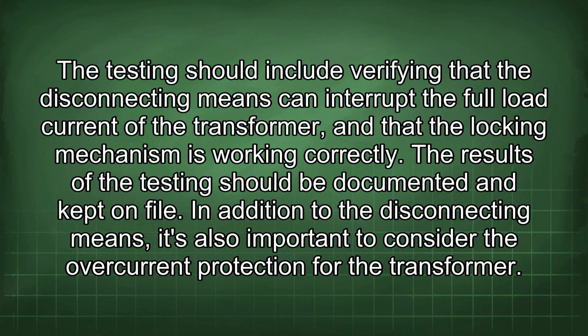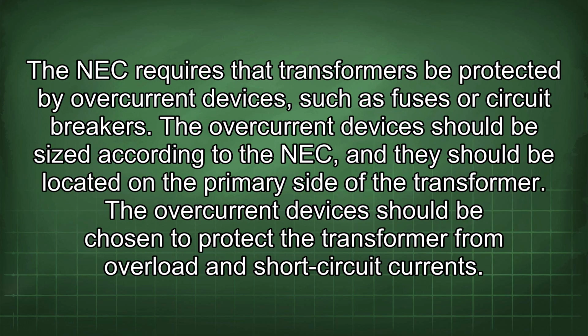In addition to the disconnecting means, it's also important to consider the overcurrent protection for the transformer. The NEC requires that transformers be protected by overcurrent devices, such as fuses or circuit breakers. The overcurrent devices should be sized according to the NEC, and they should be located on the primary side of the transformer. The overcurrent devices should be chosen to protect the transformer from overload and short-circuit currents.